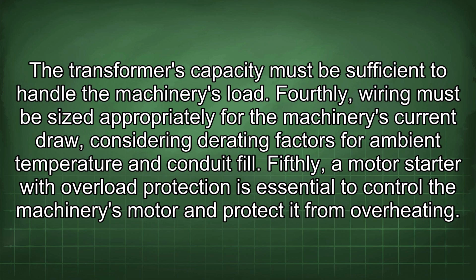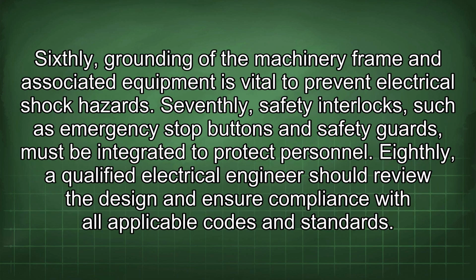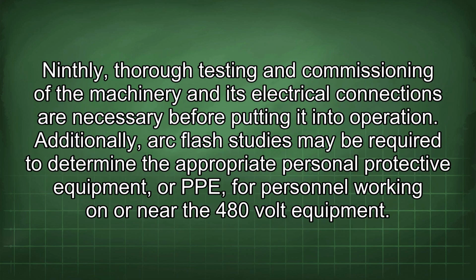Fourthly, wiring must be sized appropriately for the machinery's current draw, considering derating factors for ambient temperature and conduit fill. Fifthly, a motor starter with overload protection is essential to control the machinery's motor and protect it from overheating. Sixthly, grounding of the machinery frame and associated equipment is vital to prevent electrical shock hazards. Seventhly, safety interlocks, such as emergency stop buttons and safety guards, must be integrated to protect personnel. Eighthly, a qualified electrical engineer should review the design and ensure compliance with all applicable codes and standards. Ninthly, thorough testing and commissioning of the machinery and its electrical connections are necessary before putting it into operation.